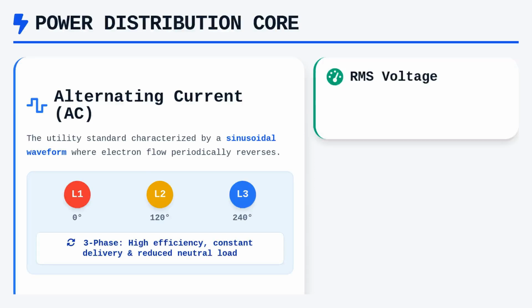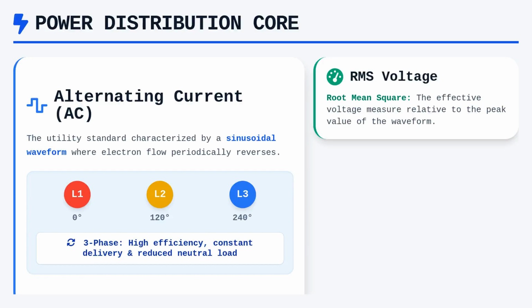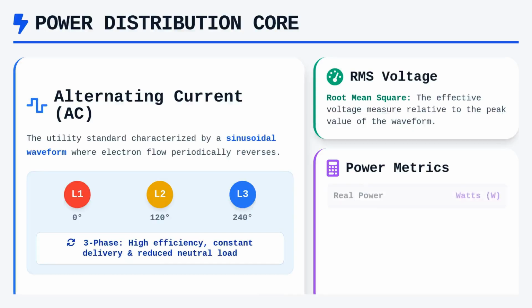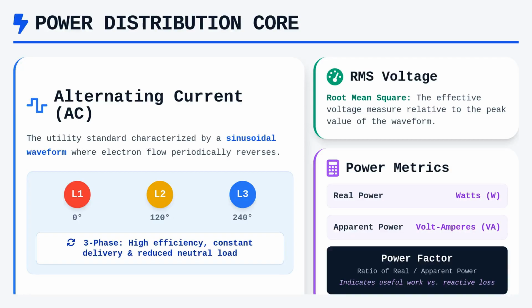A critical concept here is the root mean square, or RMS voltage, which provides a meaningful measure of the effective voltage of an AC waveform relative to its peak value. When calculating the power delivered to an equipment rack, you must distinguish between real power measured in watts and apparent power measured in volt amperes. The ratio of these two values is the power factor, an essential metric that indicates how much of the energy being drawn is actually performing useful work versus being stored or lost as reactive power due to inductive or capacitive loads.